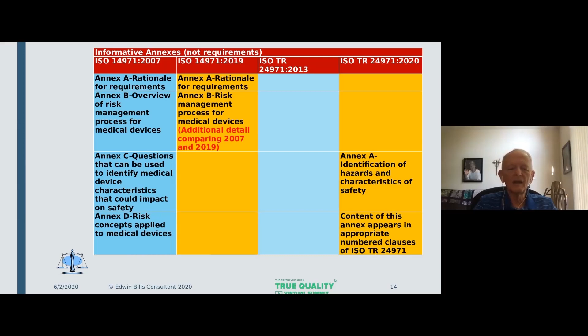The next one, which would have been Annex E, which was hazards, foreseeable sequences of events, and hazardous situations, now appears in two places. Fundamental risk concepts in 24971, which is Annex C, and that Annex C has been updated, and there is a great deal of what was in the annex in 14971:2007, but not all of it. There's more of it that also appears in 5.4 and 5.5 of 24971:2020. So there's a lot of information on identification of hazards and risk estimation there.